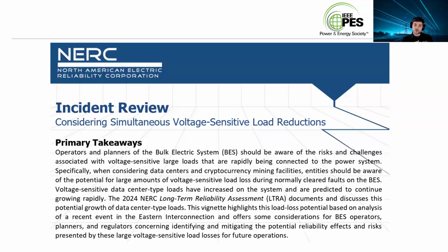It would help to get good dynamic models and EMT models of these loads now, but something to be aware of is that there's a lot of different versions of it. Not everybody uses UPSs on their servers, depending on the application. A lot of the big entities design their own equipment, so while you can purchase some off the shelf, other people may have custom designed equipment. So what's applicable in one data center may not be applicable in another.